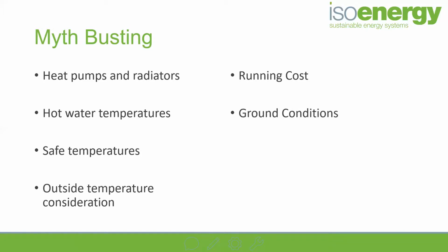So you might find that in an existing property, there are rooms which are cold. They have 1, maybe 2 radiators in, but they are cold rooms. And that's because the radiators are undersized. It's got nothing to do with the source temperature, because you may have a boiler in there at the moment that's providing 70 degrees to those radiators, but they just aren't large enough to provide enough heat into that space. So it all comes down to sizing of the heat emitters.